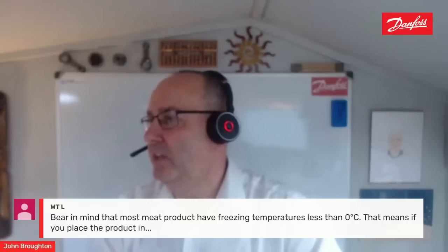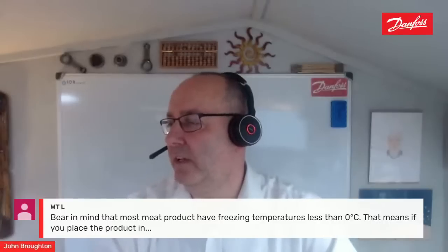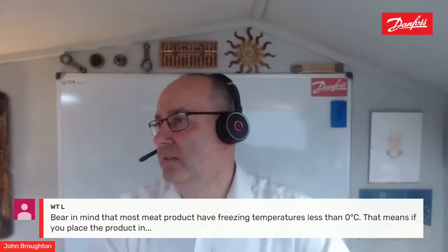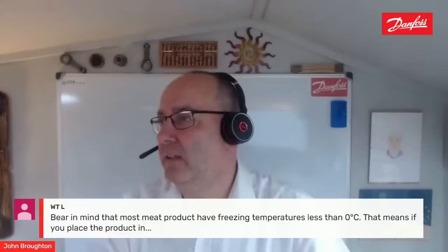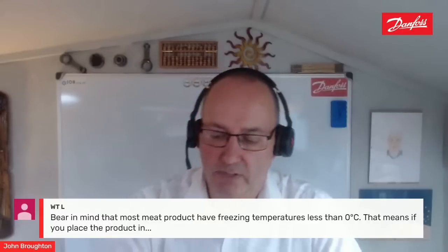And we've got Warren coming in here. Bear in mind that most meat products have freezing temperatures less than 0°C. That means if you place the product in at zero, it will have a latent load. Yeah, beef is freezing 2.8. Pork is freezing minus 1.7. Yeah, correct.